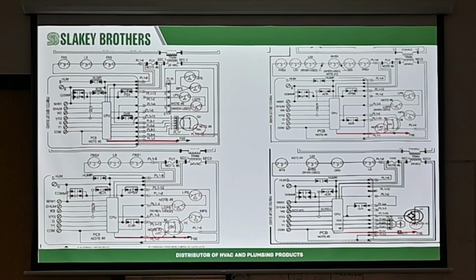And the problem is that the wire is pulled out a little bit, and it's not making contact to your board. So, process of elimination for, say, a pressure switch fault. I have 24 volts here, 24 volts here, 24 volts everywhere. I'm following my schematic and following power coming back. I confirm that I got power everywhere. I confirm that my connections are good. For instance, I can look here and check continuity between a couple points and show that the circuit is complete before the high pressure switch and is complete on the low pressure switch.